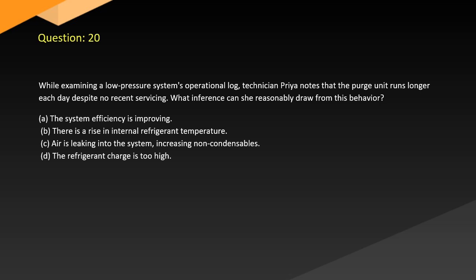Question 20. While examining a low-pressure system's operational log, technician Priya notes that the purge unit runs longer each day despite no recent servicing. What inference can she reasonably draw from this behavior? A. The system efficiency is improving. B. There is a rise in internal refrigerant temperature. C. Air is leaking into the system, increasing non-condensables. D. The refrigerant charge is too high.